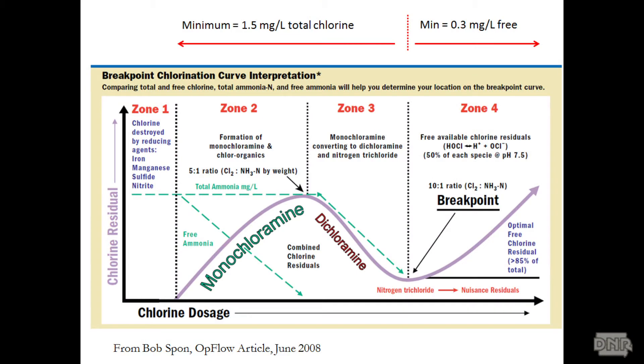In Iowa, a system that treats their water must disinfect unless the treatment is a package unit. The minimum chlorine levels are 0.3 mg per liter of free chlorine or 1.5 mg per liter of total chlorine. The level depends on if you are using free chlorine or chloramines in the disinfectant. There will be more on this later.